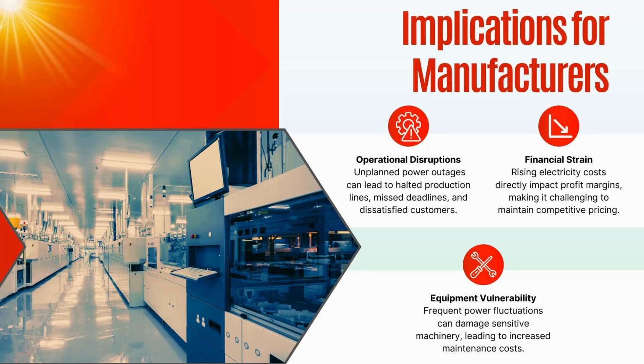By default, a lithium battery, which is the predominant technology available and adopted today, should not be discharged less than 20%. So often you'll hear people talking about 80% depth of discharge. What that means is if a battery is 100 kilowatt hours, you do not want to discharge more than 80 kilowatt hours, so there's always a 20% reserve in place.